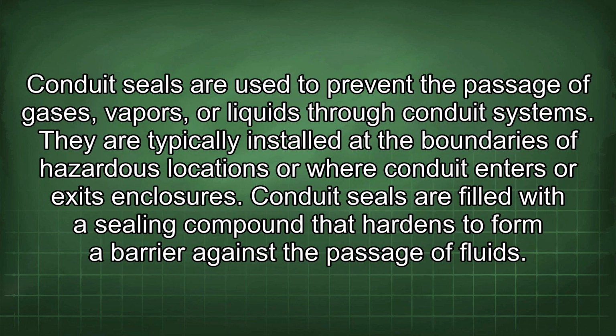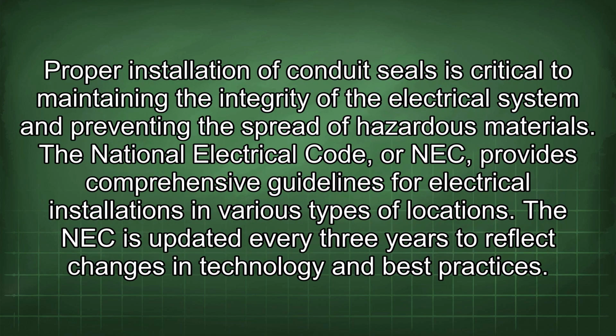Conduit seals are used to prevent the passage of gases, vapors, or liquids through conduit systems. They are typically installed at the boundaries of hazardous locations or where conduit enters or exits enclosures. Conduit seals are filled with a sealing compound that hardens to form a barrier against the passage of fluids. Proper installation of conduit seals is critical to maintaining the integrity of the electrical system and preventing the spread of hazardous materials.